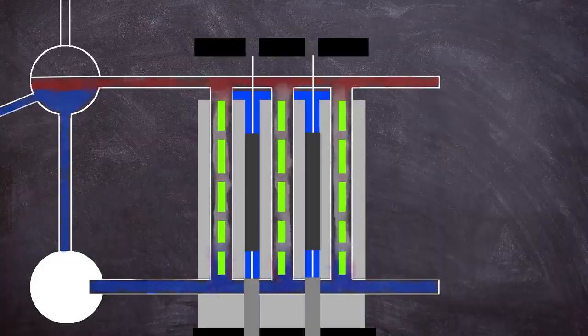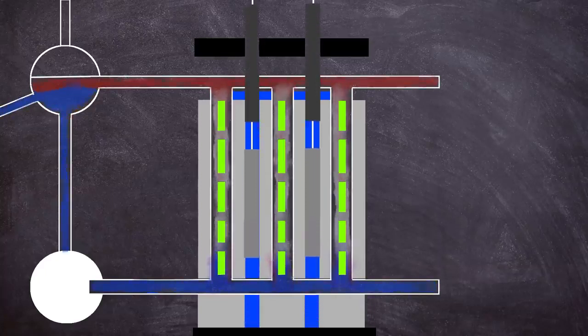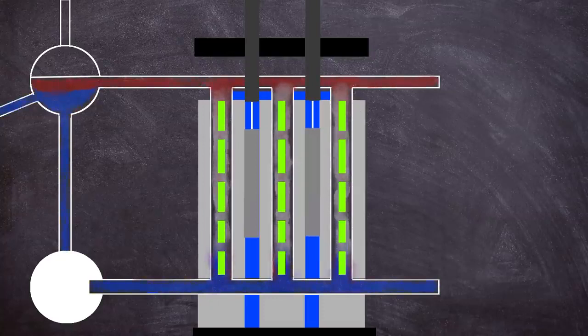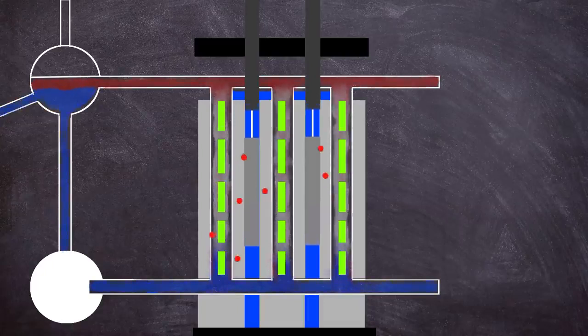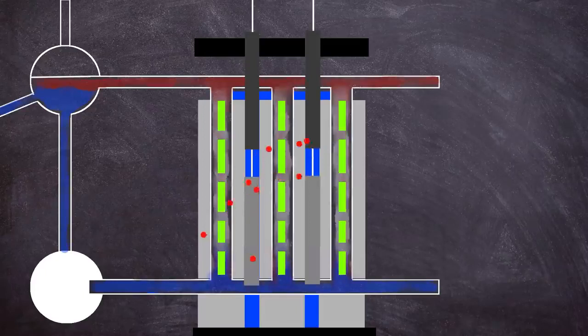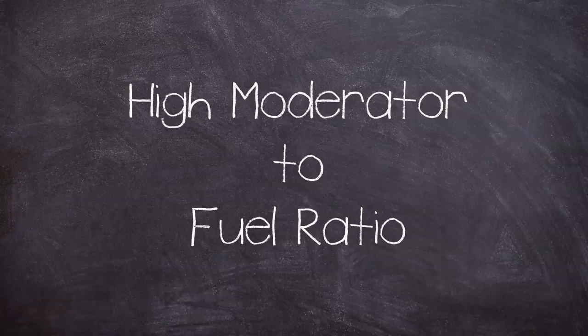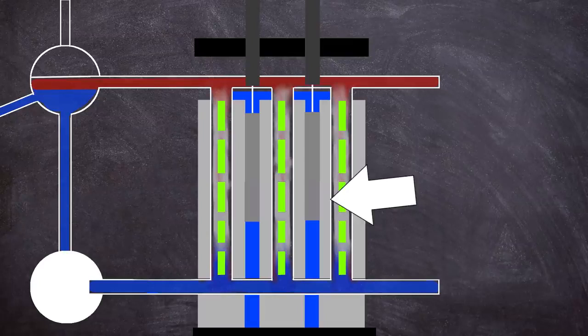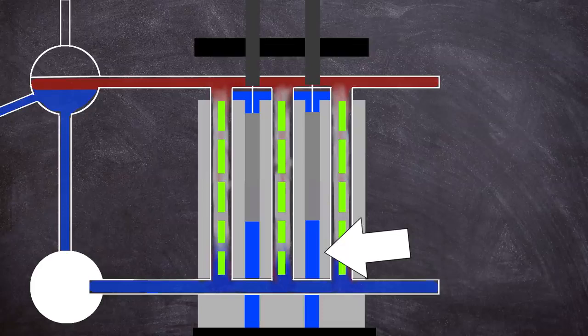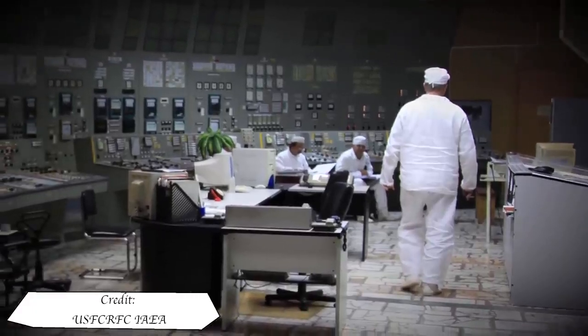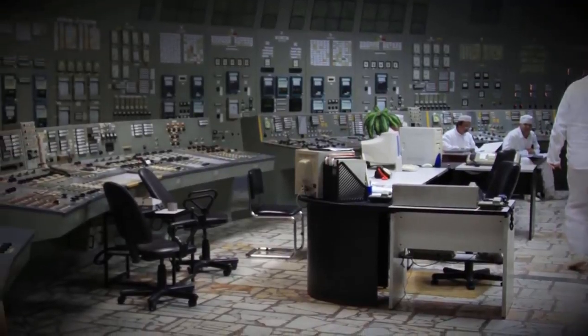The dimensions of the rod and displacer were that when the control rod was fully extracted, the displacer sat centrally within the fueled region with 1.25 meters of water at either end, but this setup could cause a positive scram effect. On receipt of a scram signal causing a fully withdrawn rod to fall, water was displaced from the lower part of the channel as the rod moved downwards, causing a localized insertion of positive reactivity in the lower part of the core. This was because the RBMK had a high moderator to fuel ratio, meaning the lower part would experience a spike in reactivity as the graphite displacer entered it, replacing neutron absorbing water with neutron moderating graphite. But this situation was only dangerous at certain power levels, meant to be mitigated by knowledge and training of operators and management.